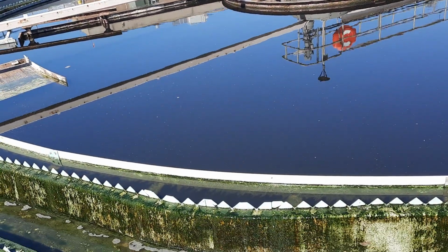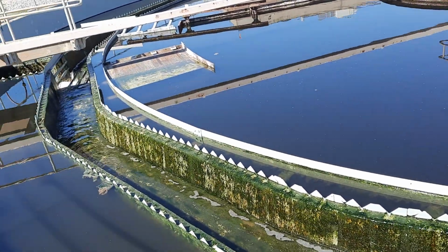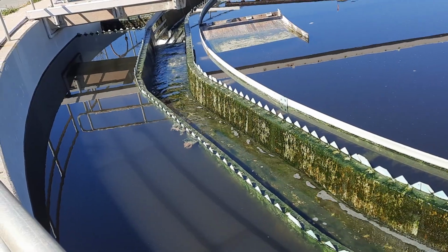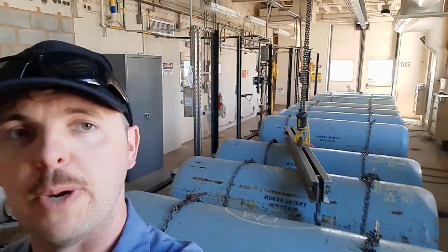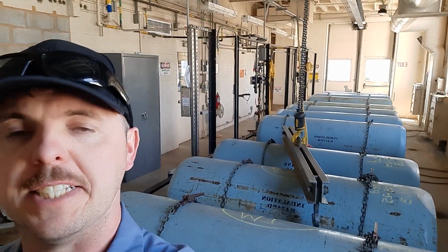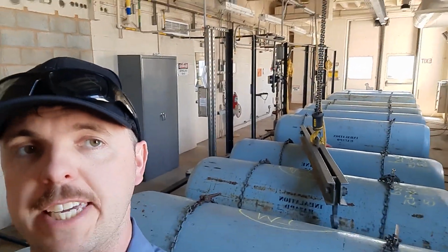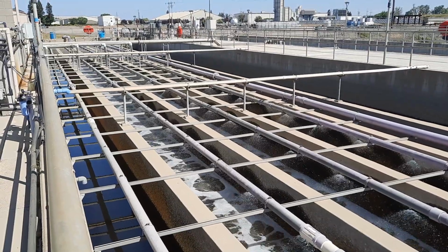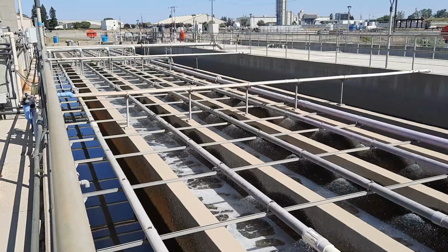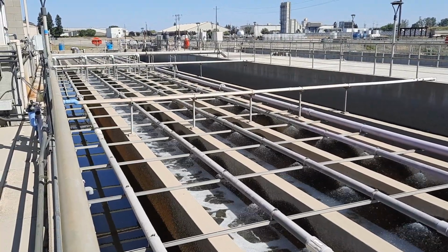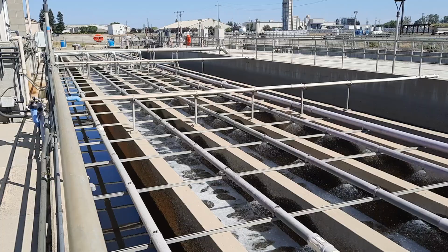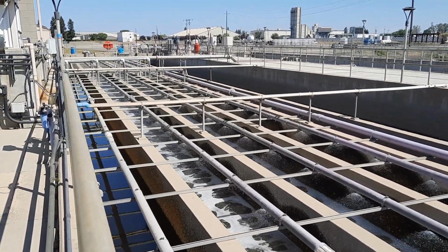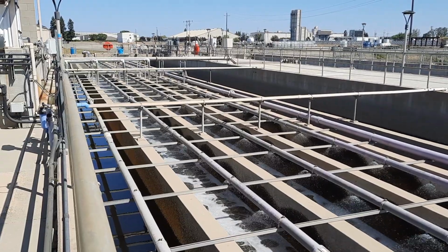From the secondary clarifiers, sludge settles out and the clear water flows out of the secondary clarifiers into our contact basin. On the way to the contact basin, the secondary effluent is mixed with chlorine that's going to kill any pathogens left in the water stream. Here you can see our contact channels where the secondary effluent is going to flow through. After being injected with chlorine, it's required to meet a certain detention time where it's in contact with the chlorine. The minimum is 2 hours. We don't come anywhere near that. We're way above that, so we're good.